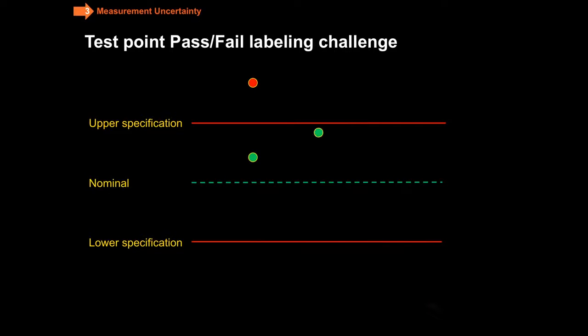Where the confusion comes about is when you have a measured point that is either just barely inside or just barely outside the specification. Then the question is, can I believe that measurement? We never know exactly the true result. So the best you can do is to come up with a statistical interval over which you can say the measurement is at least between here and here, and that's really what measurement uncertainty is all about.